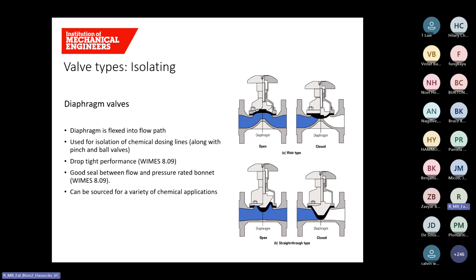Another type of isolation valve is the diaphragm valve. These valves have a diaphragm which is flexed into the flow path and isolates the flow. They're typically used for chemical dosing lines, and they can be used in place of pinch valves or ball valves. They're drop tight, so perform a very good seal. They can be used for a number of different chemicals, and depending on the application, the diaphragm itself can be changed for the most suitable material.